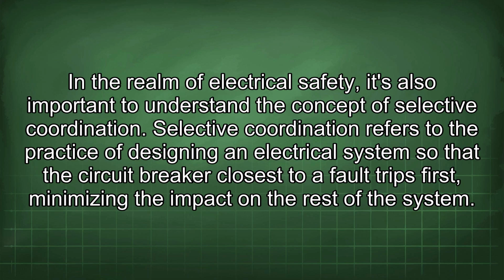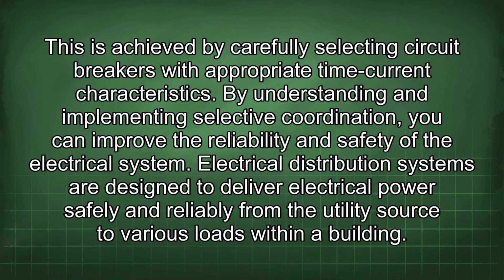In the realm of electrical safety, it's also important to understand the concept of selective coordination. Selective coordination refers to the practice of designing an electrical system so that the circuit breaker closest to the fault trips first, minimizing the impact on the rest of the system. This is achieved by carefully selecting circuit breakers with appropriate time current characteristics. By understanding and implementing selective coordination, you can improve the reliability and safety of the electrical system.